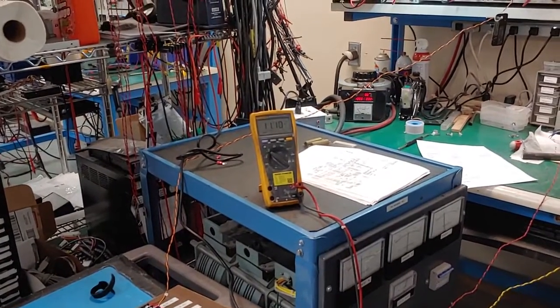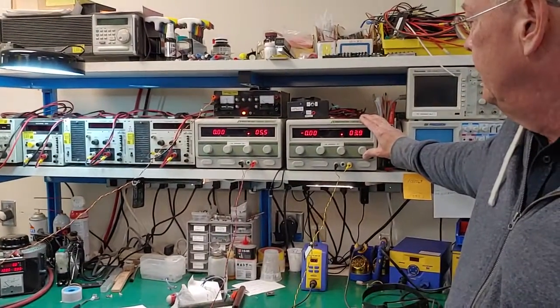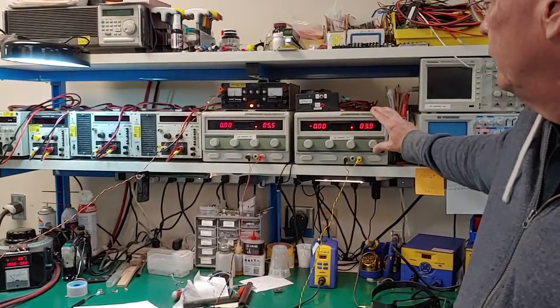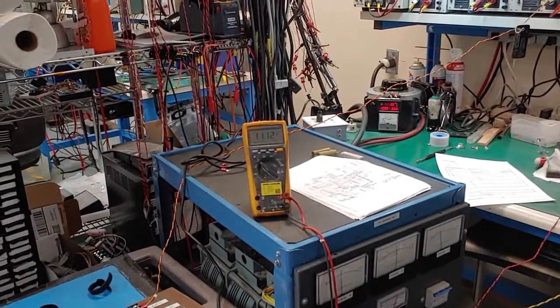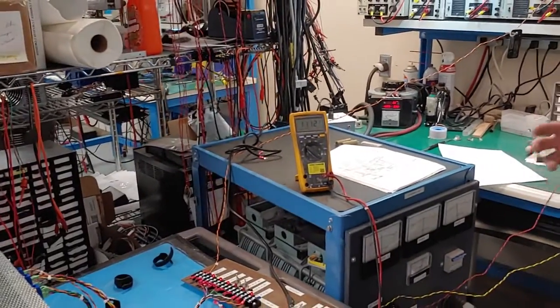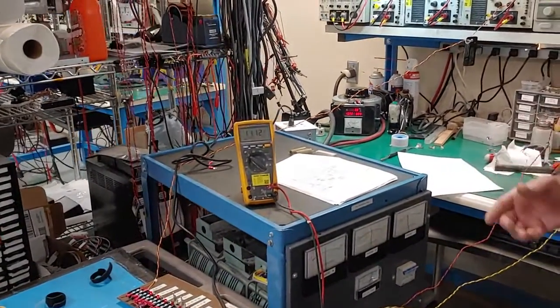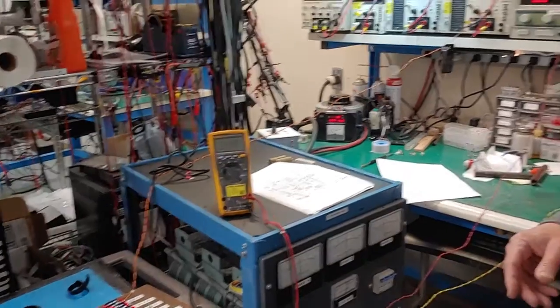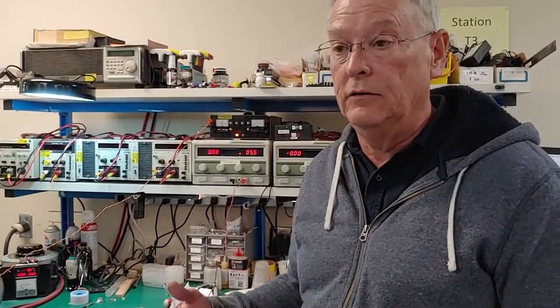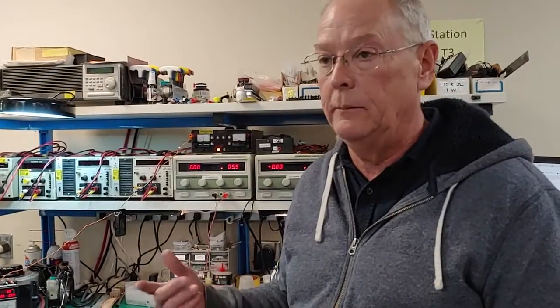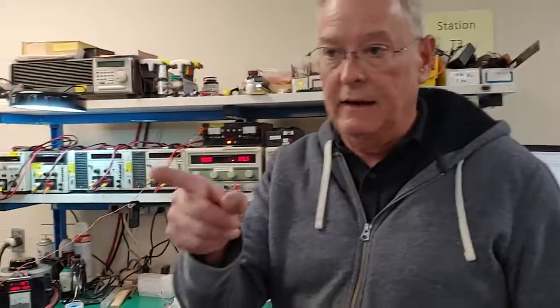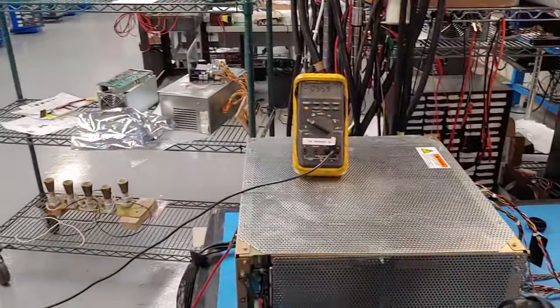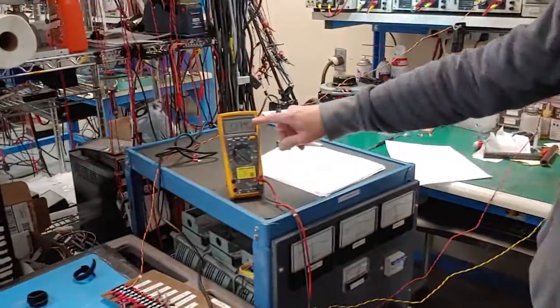So in other words, if I increase this all the way up to 40, it's asking for 40 milliamps of current. And the way it would normally do it if it was closed loop is the heater would heat up in your X-ray tube. The high voltage current would increase because the effective resistance starts to drop as we get more emissions. Keep in mind, I have a static load, so I don't have the ability to change the current setting. That's why we're open loop. All right, so there we go.